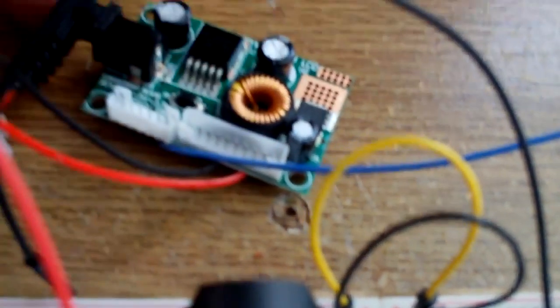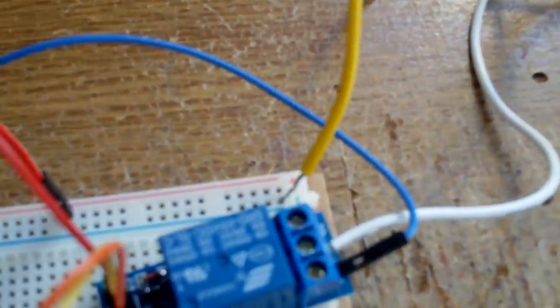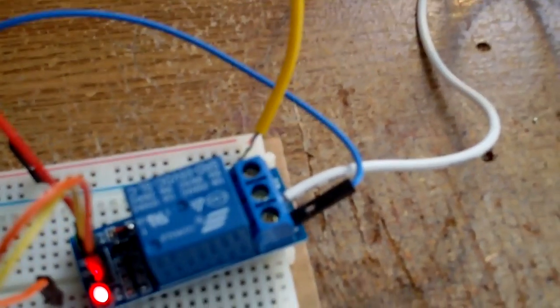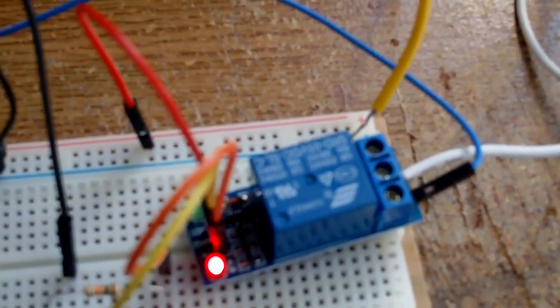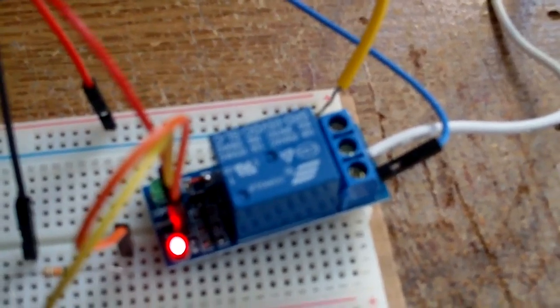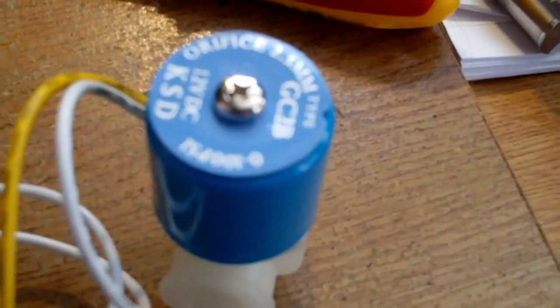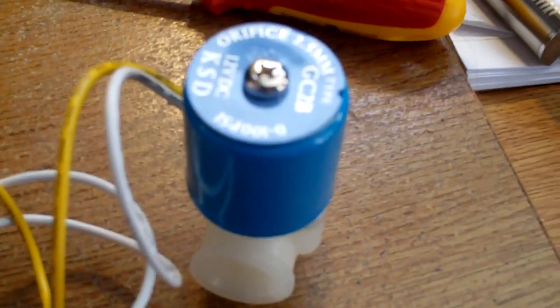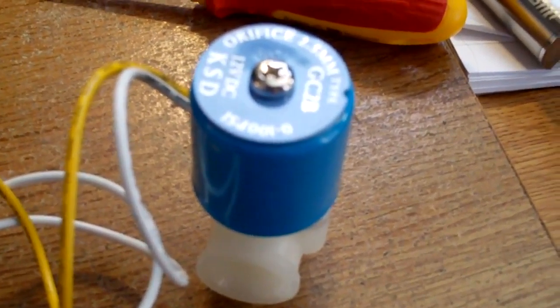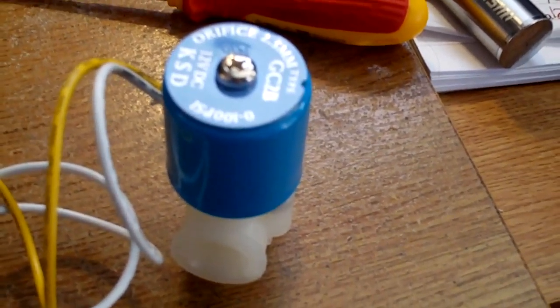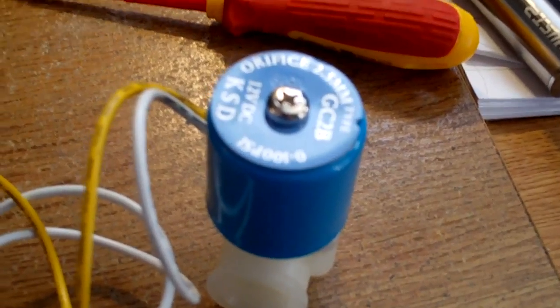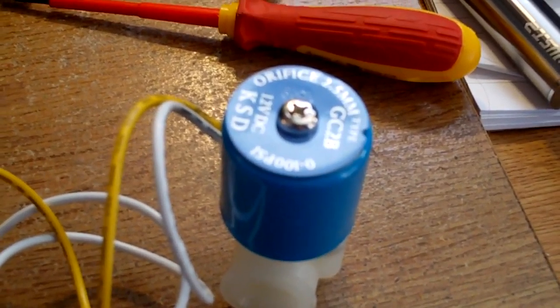The other power I'm taking off this unit is the blue wire, this one. And it's 12 volts which is the voltage required for the solenoid. And after a little bit of trying to remember my basic Ohm's law it's this guy here, 12 volt DC and the winding is, what was it now, 24 ohms. So that tells me it's going to draw about 500 milliamps or half an amp.